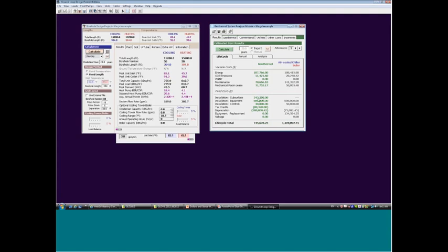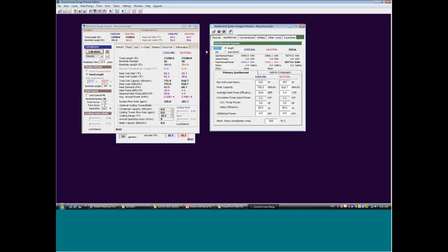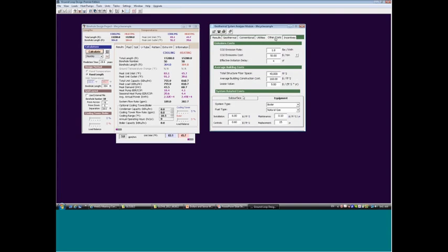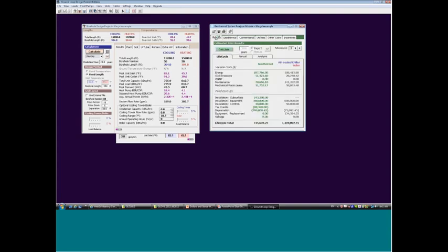Then we have our fixed costs. They're saying that it's about $250,000 to install this loop field. And again, that comes from 15,200 feet times 16 bucks a foot. Mechanical equipment's about a little over $500,000 for both conventional and geo. Controls costs are here. We have our tax credits. Again, it's in parentheses because it's a minus, meaning it's being subtracted out from the overall cost equation.